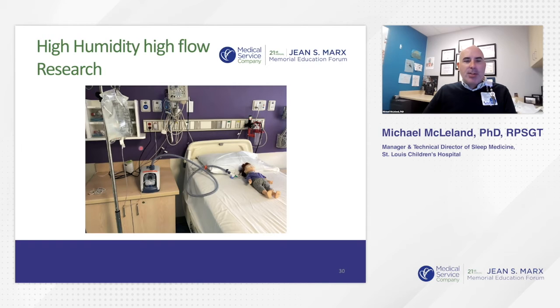When you're doing high flows, you can't just have water in the humidifier chamber itself. You really have to bleed in water because it goes through water so much due to the high humidity. So you really have to have a lot of water to make sure you don't burn up your humidifier system. So you just keep it flowing in.